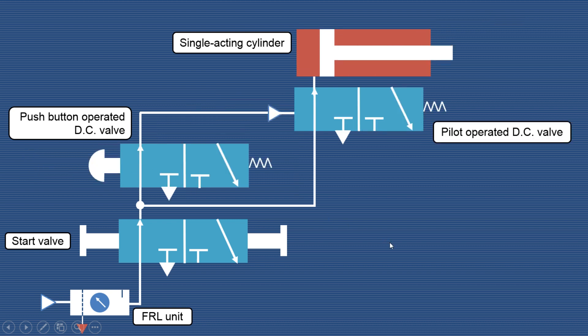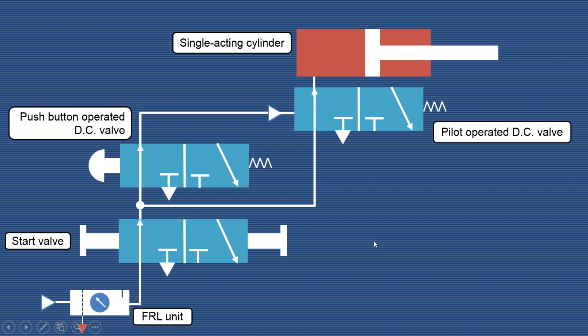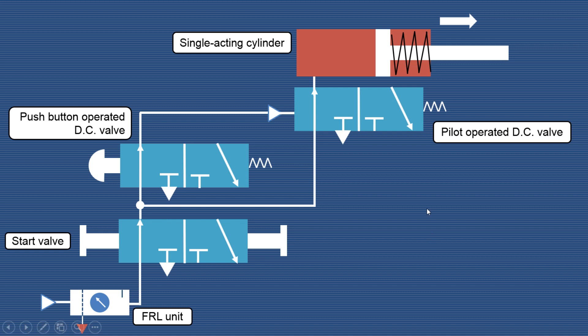When we operate the push button, the left envelope mode comes into action. Air from the FRL unit enters through the left envelope of the push button operated DCV into the pilot port of the pilot operated direction control valve, causing its left envelope mode to come into action. Once that is done, air from the main line enters through this path and is admitted on the cylinder side of the piston, causing the piston to move in the forward direction, compressing the spring — giving the forward stroke as shown.